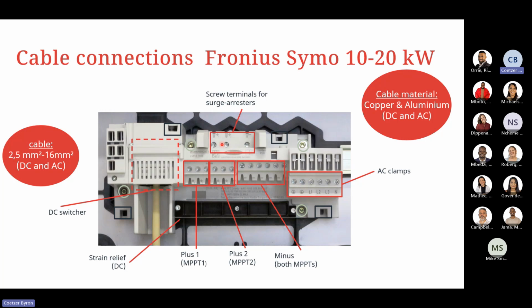So what happens is the MPPTs are split. Your 1 to 3 is MPPT 1, for example, and 4 to 6 is your MPPT 2 range. Whereas on the negative side, they are both sharing a common busbar. So it's not that drastic for the negative side to be kept in from 1 to 1, for example. But if you can, please maintain connection point 1 to 1, 2 to 2, and so forth.